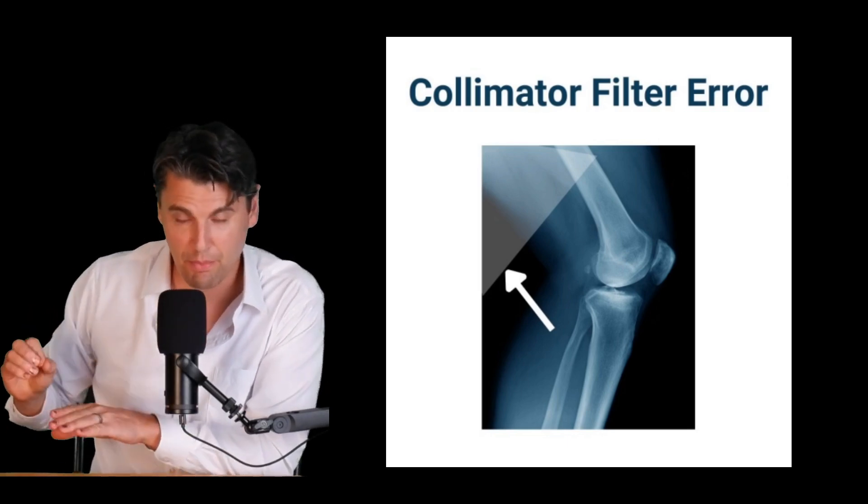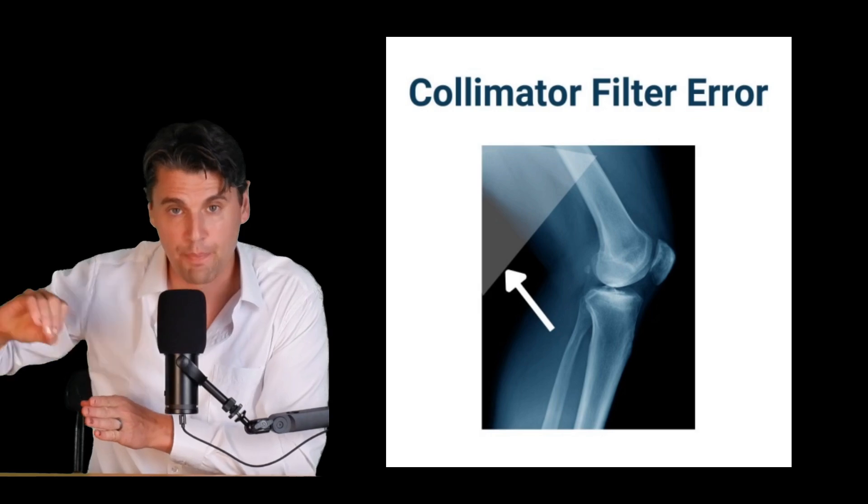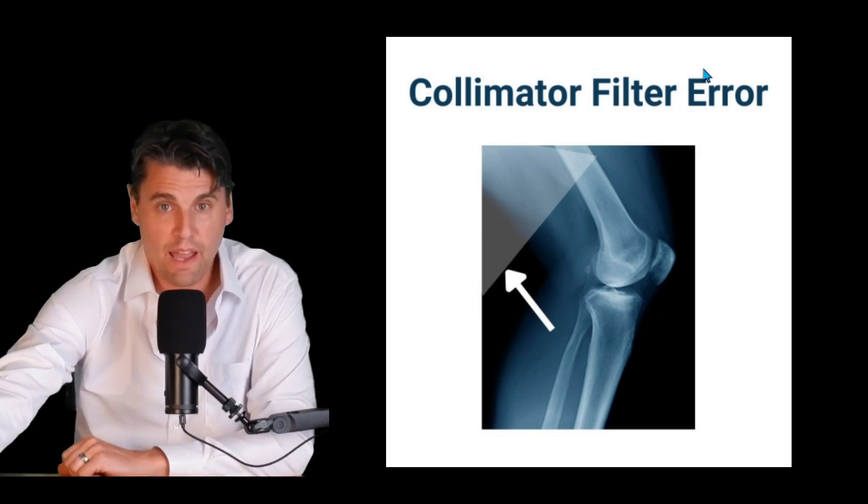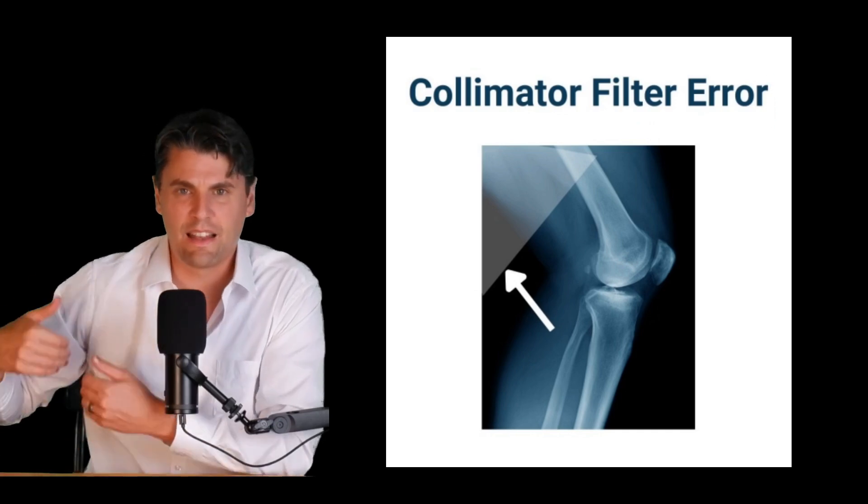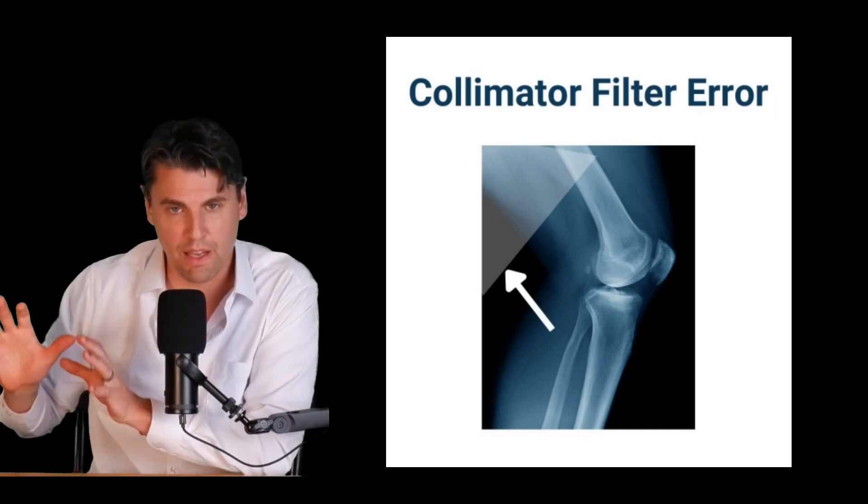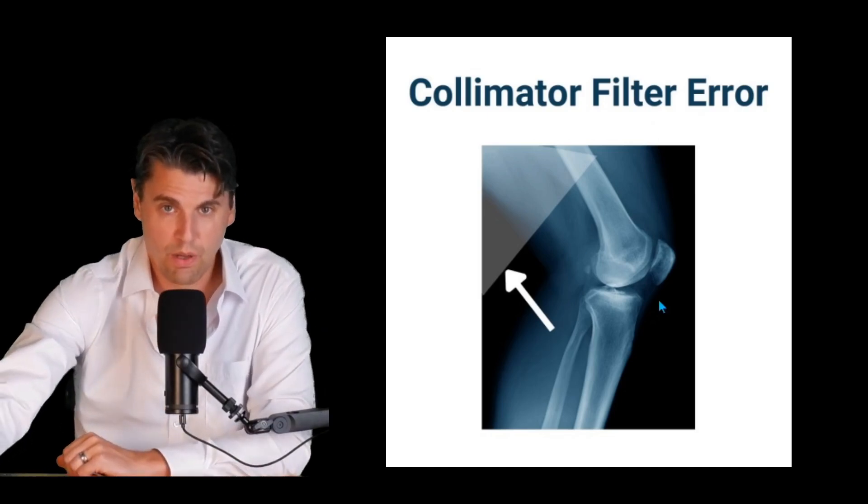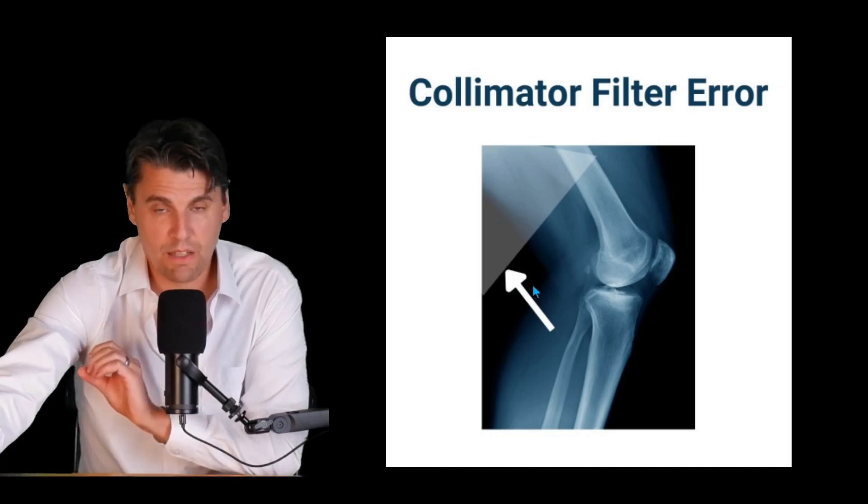If part of the collimator assembly had come loose and it is actually obscuring part of the field of view that could lead to an overlap in your image something like this. Again this is not extremely common but if you see something like this it is the case that you would want to let the manufacturer know that they could come and do quality assurance and potentially make updates to the system as necessary.